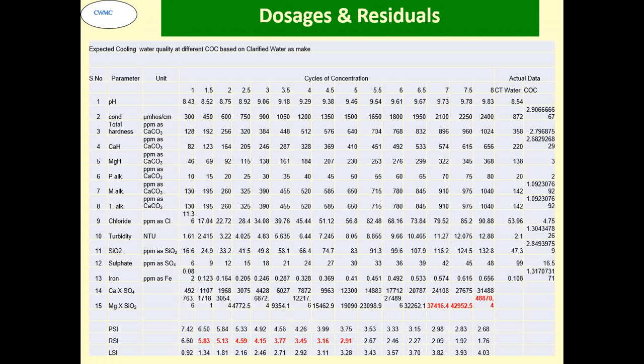This is the typical cycles of concentration that has been carried out, and normally what you see down below, the Ryznar stability index in the red color, I have put 2.91. Normally it is not recommended that we go beyond RSI of 3. Lower than 3 RSI are very difficult to be treated by chemical treatment. We have to then go for the softening and other things to operate on that.